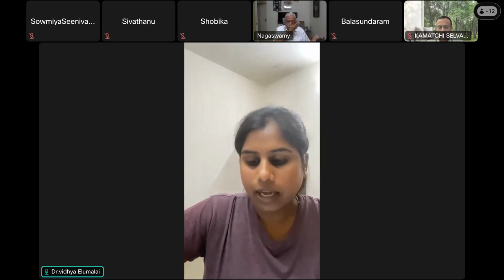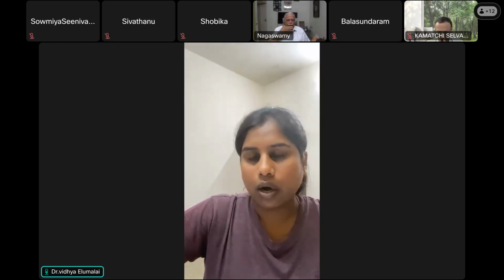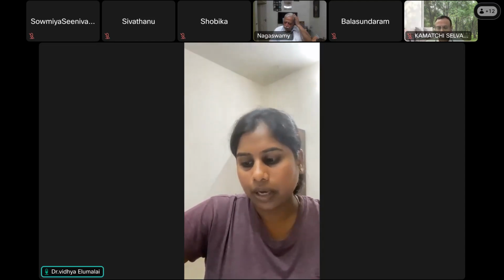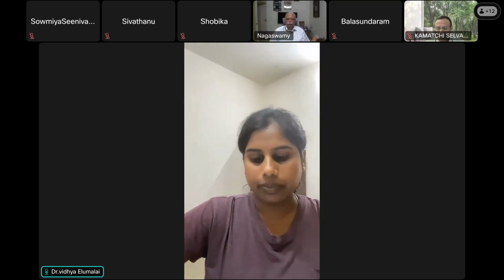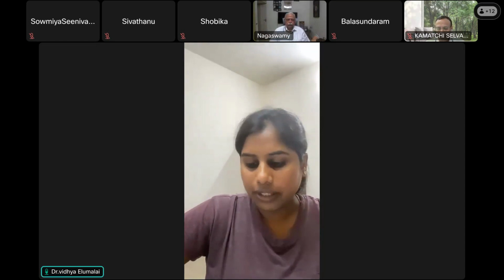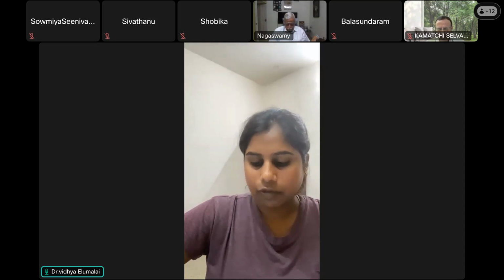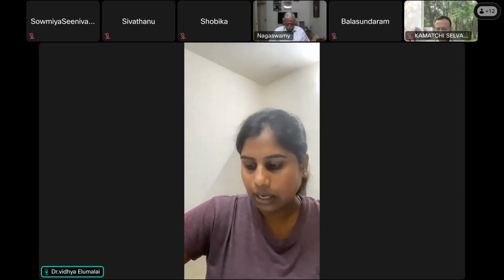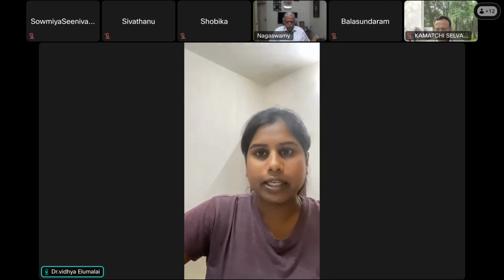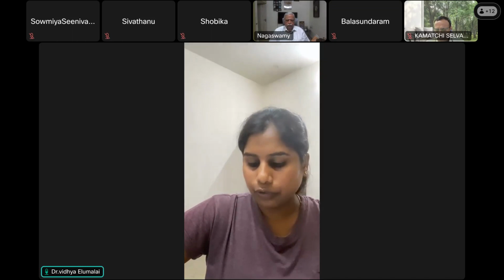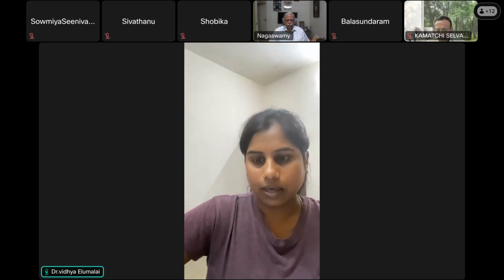Item 4, verify availability of required monitors. All are working and the limits are set and the alarms are working. Item 5, verify that the pressure is adequate on the spare O2 cylinder mounted on the anesthesia machine. Item 6, verify that the piped gas pressure is more than or equal to 50 psi or more than 400 kilopascals. Item 7 is to verify that the vaporizers are adequately filled and, if applicable, the filler ports are tightly closed. Item 8 is to verify that there are no leaks in the gas supply line between the flow meter and the common gas outlet.